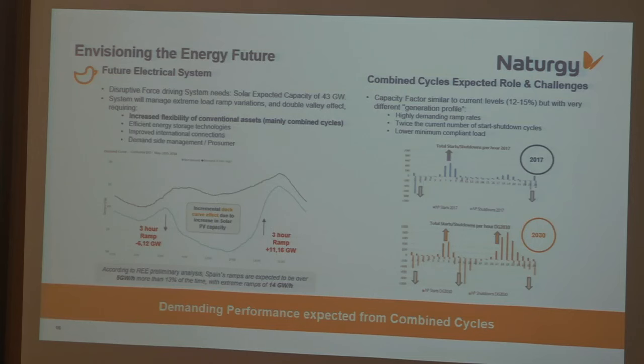They will also need lower minimum loads, which will be beneficial for the system and for the plants. The system will benefit from greater inertia and greater spinning reserves. The power plants with lower minimum loads will also benefit from less cycling and less wear and tear, and economic benefits from being parked at low load instead of having a startup cost.